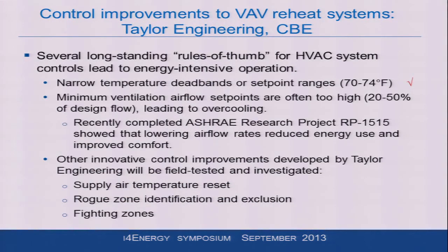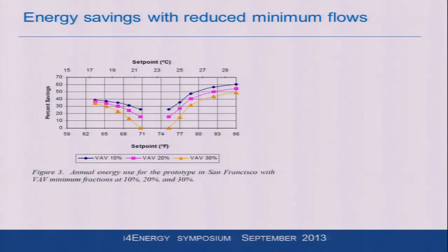But the other things we are interested in are various ways of more intelligently resetting the supply air temperature so your chiller doesn't have to run as much, finding rogue zones that may take command of the whole building and force the supply air temperature or the supply volume to be too high as a result of a bad reading or something wrong, and fighting zones where you're heating and cooling at the same time, and this goes on all the time. So I'll talk a little bit about just the low minimum. The low minimum reduction is really important. So here we've got 10, 20, and 30%. This is the minimum flow that's capped. You can't go below that.